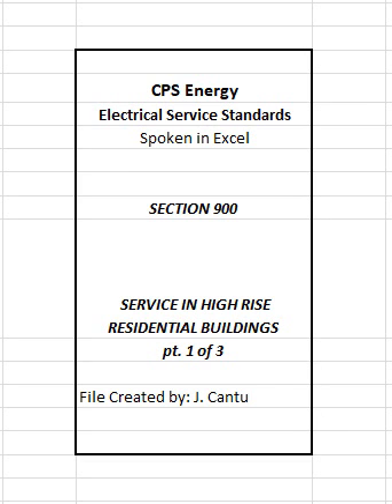Exception: where justified by demand load, and with special approval of CPS Energy, house loads may be supplied from a separate 480Y/277 volt, 4-wire Y transformer supplied by CPS Energy. Customers' 480Y/277 volt service equipment shall be co-located with customers' 208Y/120 volt service equipment. Metering for house loads served with this type of service may be located at the transformer secondary or at customer's service equipment location.